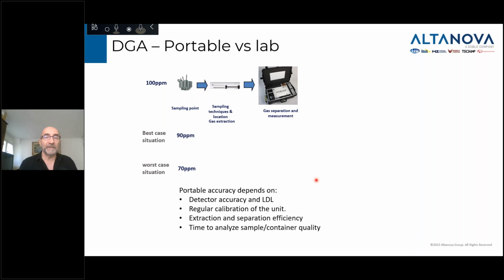Also, how often the system is calibrated. As I said earlier, every system starts losing accuracy from the moment you buy it. That's the reality of an electromechanical system. If, as time goes on, you cannot calibrate it regularly to bring back the accuracy it had when the equipment was brand new, that will have a big impact on the accuracy of the measurement. Also, what is the extraction and separation efficiency? There are different ways of extracting the gases. Mostly everyone today is using headspace, but the length of the headspace extraction has an effect on how much gas is extracted, especially of the heavy gases. Heavy gases are much more difficult to extract out of the oil than light gases like hydrogen and carbon monoxide.